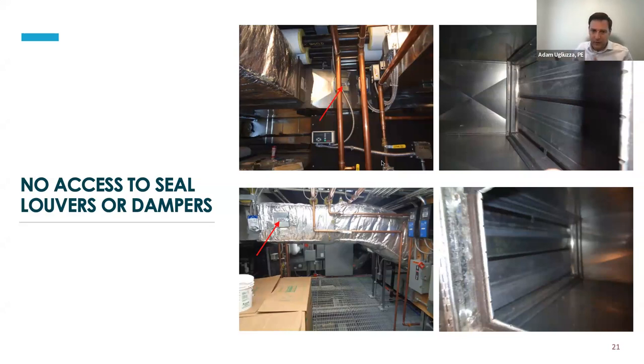Or it just, the way that they've sealed the ductwork to the exterior wall might limit you. You just don't have the access to do it. So in this case, confirming that those dampers are shut is very, very important. If you can't seal up the louver, because sometimes even if the control engineer thinks it's completely shut, you can find that it's not. It's saying it's 100% shut, but it might be 50% open or completely open. I've had that happen a number of times. So if you can't seal them up, you've got to verify that the dampers are shut completely.